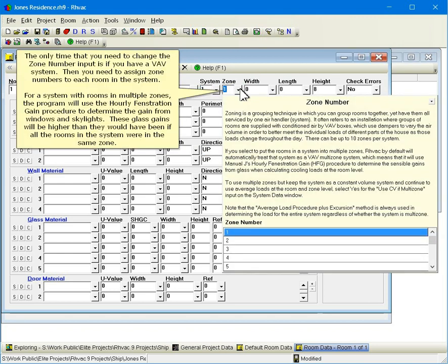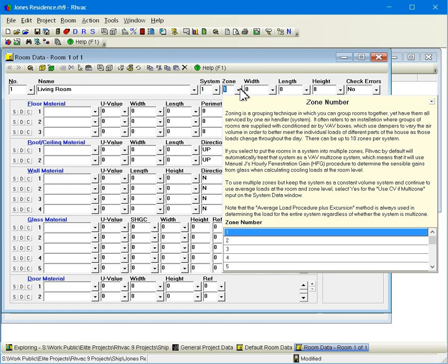The only time that you need to change the zone number input is if you have a VAV system. Then you need to assign zone numbers to each room in the system. For a system with rooms in multiple zones, the program will use the hourly fenestration gain procedure to determine the gain from windows and skylights. These glass gains will be higher than they would have been if all the rooms in the system were in the same zone.